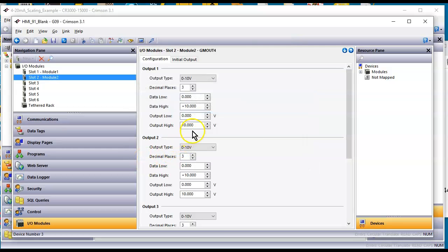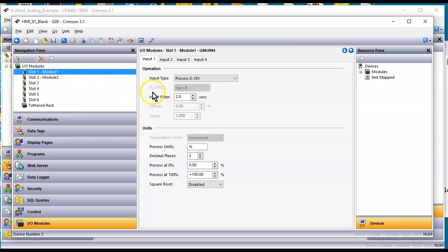Analog output right there. Perfect. So I want you to notice Red Lion does this all the time. They have these 0 to 10,000 numbers in here. And if I go over to this guy, my analog input, you can see right here, I'm saying the word 10,000, I'm going to be honest here, but it shows up as 100.00. But in reality, it's an integer value, 0 to 10,000. If you remove that decimal point, this number is 10,000.